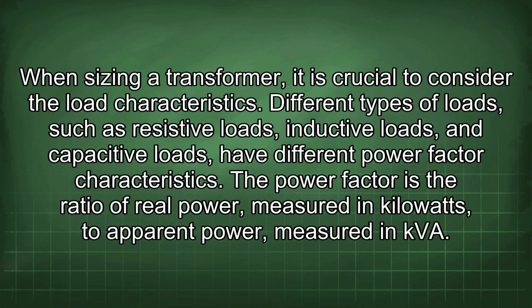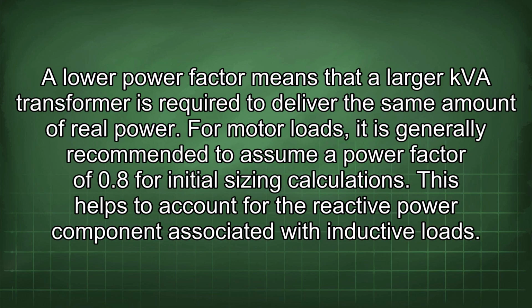When sizing a transformer, it is crucial to consider the load characteristics. Different types of loads, such as resistive loads, inductive loads, and capacitive loads, have different power factor characteristics. The power factor is the ratio of real power, measured in kilowatts, to apparent power, measured in kVA. A lower power factor means that a larger kVA transformer is required to deliver the same amount of real power. For motor loads, it is generally recommended to assume a power factor of 0.8 for initial sizing calculations. This helps to account for the reactive power component associated with inductive loads.